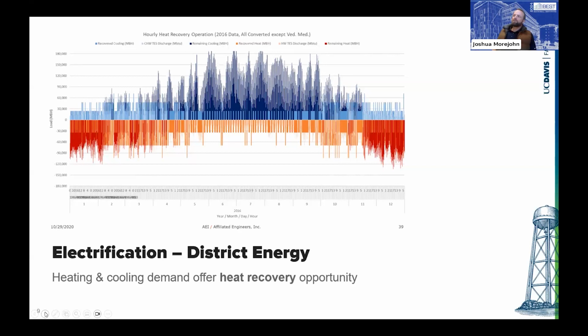This just shows some of that opportunity in terms of heat recovery. And the blue on the top of the chart is the campus cooling demand over the course of a year, 8760 hours. And the light blue is the cooling that can actually be used for heat recovery. One of the mind shifts you have to make is that the cooling system is actually a heat collection system. You're collecting heat from all your campus buildings. Unfortunately, without having heat recovery chillers, you're just throwing that heat away through the cooling towers. It's a low grade heat, so it's not very useful unless you can do something with a heat recovery chiller or a heat pump and step it up to a more useful temperature.